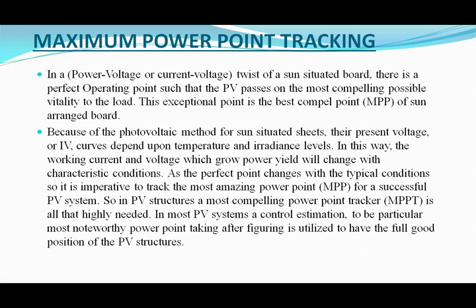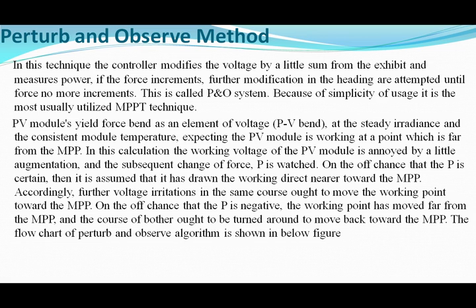In PV systems, a maximum power point tracker is highly needed. In most PV systems, a control algorithm — specifically maximum power point tracking — is utilized to take full advantage of the PV system. The Perturb and Observe (P&O) method: in this technique, the controller modifies the voltage by a small amount from the array and measures power. If the power increases, further modification in the same direction is attempted until power no longer increases. This is called the P&O method. Because of its simplicity, it is the most commonly used MPPT technique.